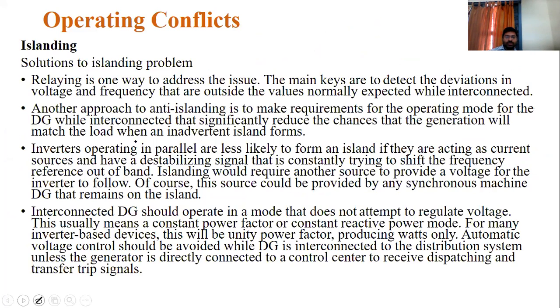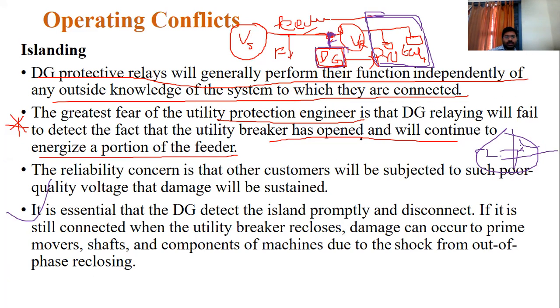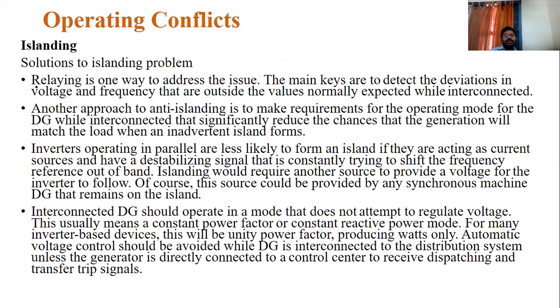So what are the solutions to this problem? How, whether the relays fail to operate? Yes, this is how the islanding problem occurs: relays fail to detect the external fault present in the feeder. So then, what are the solutions here? These are some different types of solutions to the problem. One way is the relaying, but you know that the main thing is the relay. What is another approach? Anti-islanding is to make a requirement to operate the modes of the DG interconnect that significantly reduces the chance that the generation will match the load when an inadvertent island forms. You see this?